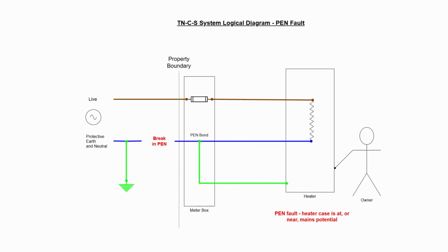However, if we now attach a person to the metal case, we have a new circuit. The new current path is along the live through the heater's resistive element, back along the neutral wire to that bond to the CPC, then along the CPC and through our person, who might be standing on the earth in a lean-to in which the heater is situated, unaware of the risk.